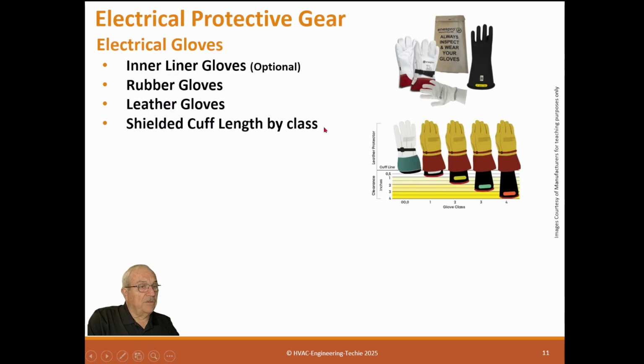So that's where there are a couple other requirements. One is shield length, the cuff. There has to be a certain protection cuff length, so the Class 4 is a much bigger glove than a Class 0 glove. Class 0 just barely exits the glove, and you can see that the next one up, Class 1, is a little longer, Class 3 is a little longer, and Class 4 is the longest. And that's to keep you from being able to brush against something that might have power on it. So it's a protective deal.